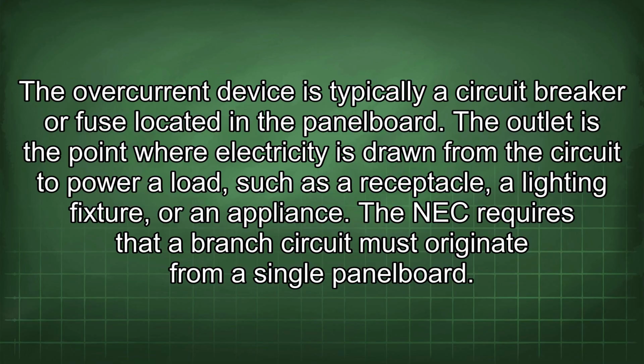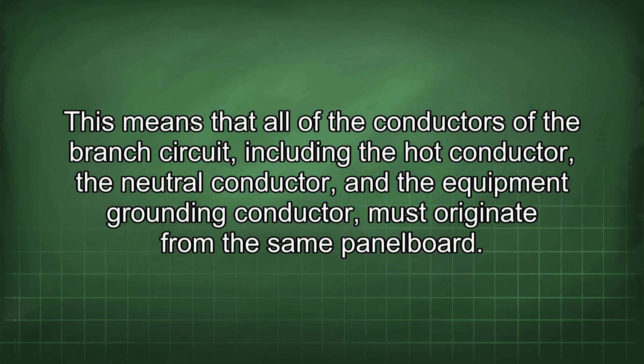The outlet is the point where electricity is drawn from the circuit to power a load, such as a receptacle, a lighting fixture, or an appliance. The NEC requires that a branch circuit must originate from a single panelboard. This means that all of the conductors of the branch circuit, including the hot conductor, the neutral conductor, and the equipment grounding conductor, must originate from the same panelboard.